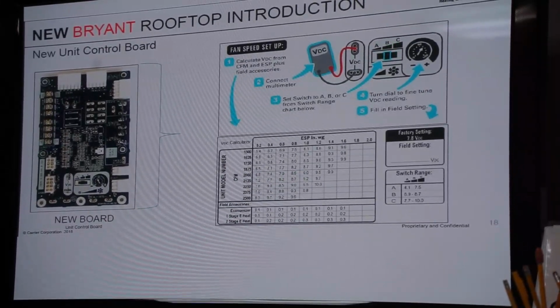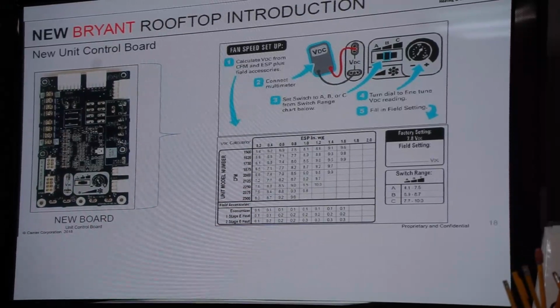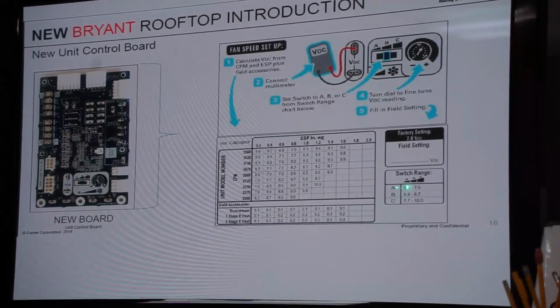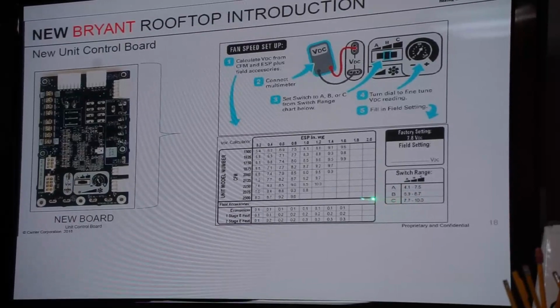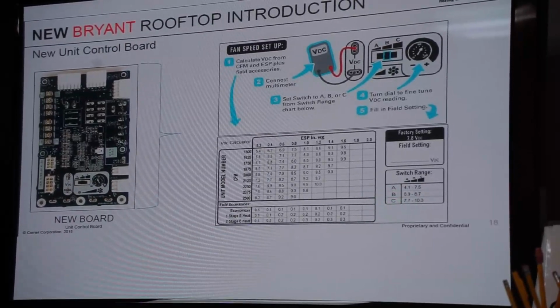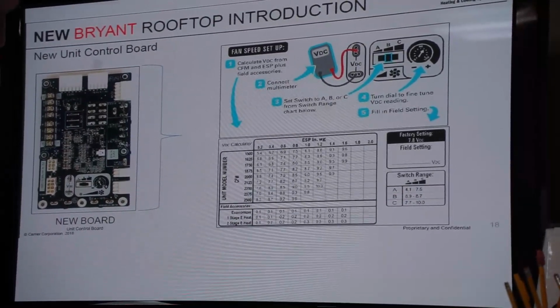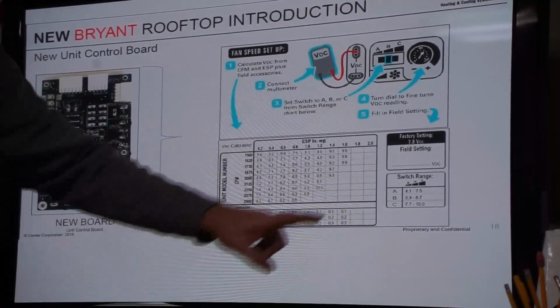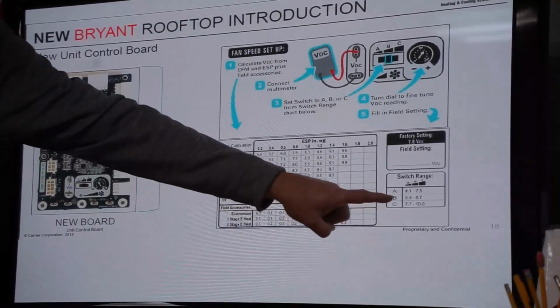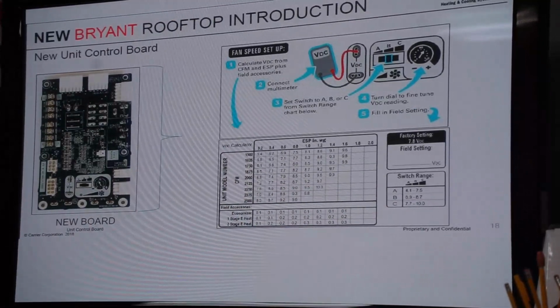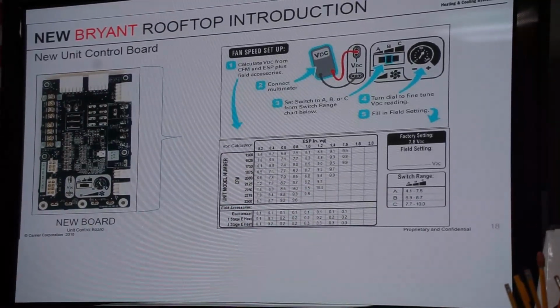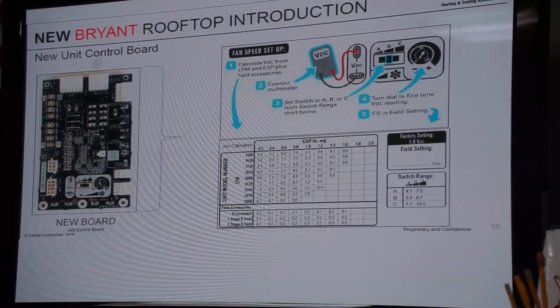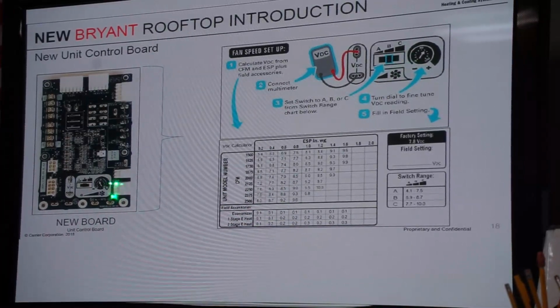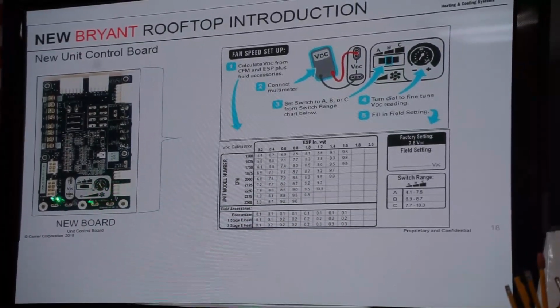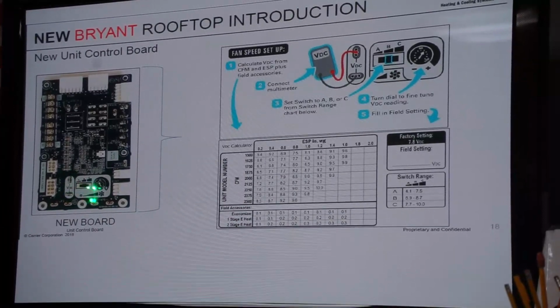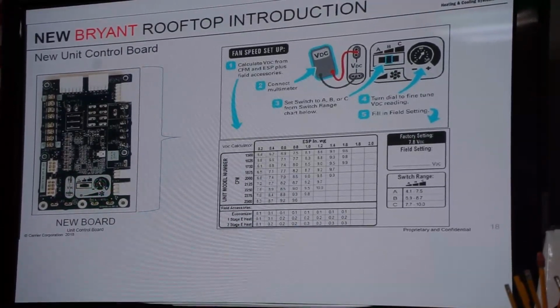The ABC switch just gives you a range. So if you look down here, A is 4.1 to 7.5, B is 5.9 to 6.9... B is 6.9 to 8.7, and C is 7.7 to 10. So in this application, I'd slide that all the way to C. I'd take my thermostat screwdriver right here with my voltmeter on these two connections and raise that up to 8.7.